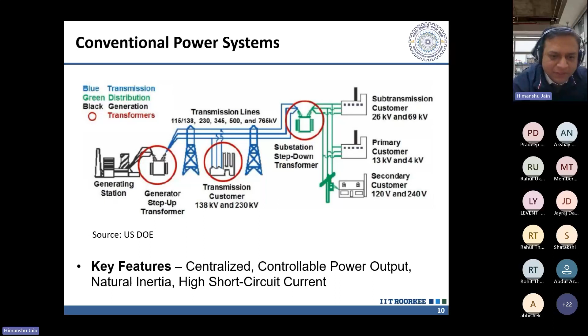We also have a lot of inertia in our system, coming from the rotating mass connected to our grid. All the generators and turbines are very heavy rotating masses connected to the grid. We also provide a lot of short circuit current, which the protective relays in your grid benefit from, as they rely on this capability of our current grid.